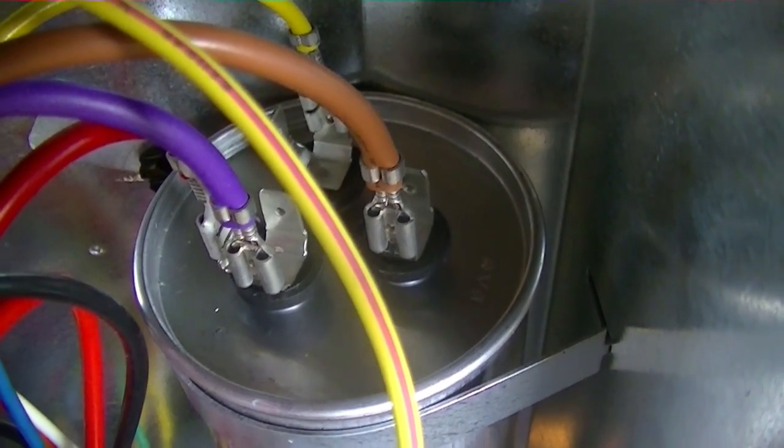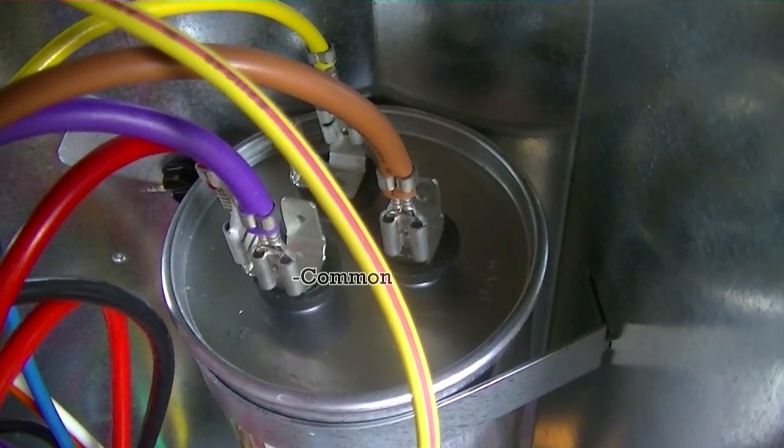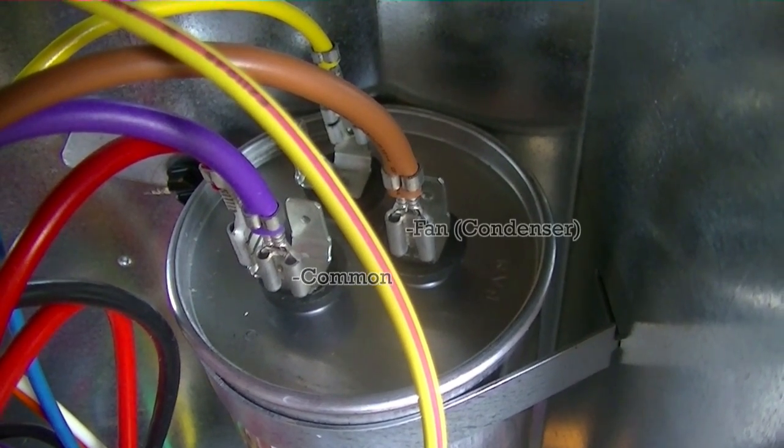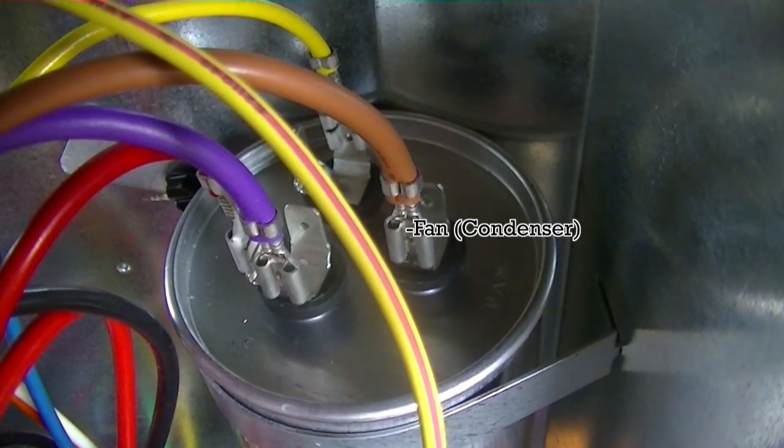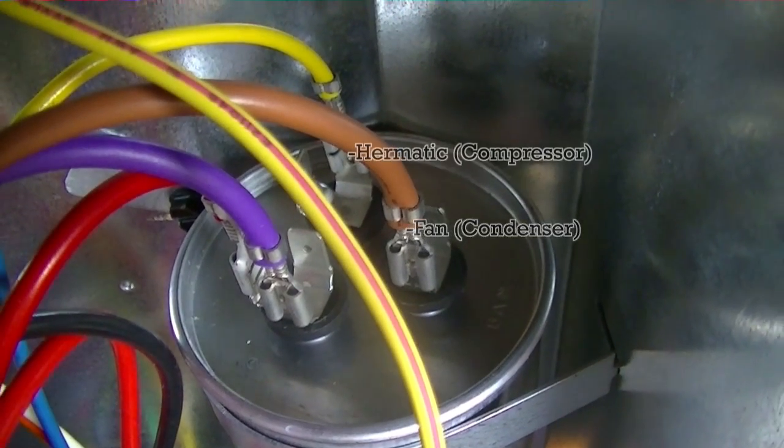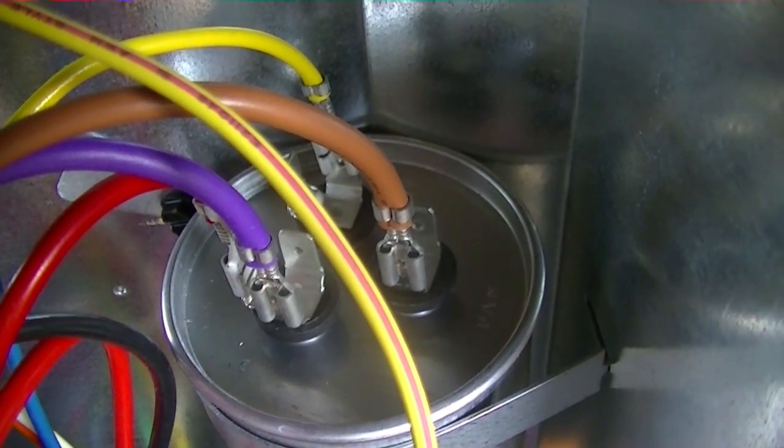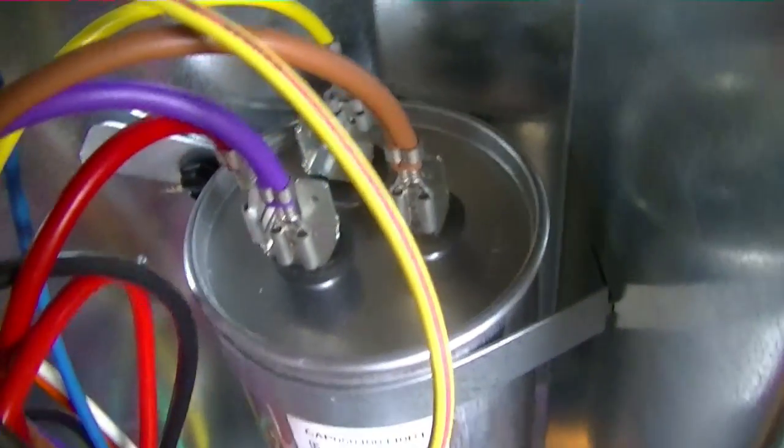Here we have our capacitor. We have the purple and red going to our common terminal. We have our brown going to our fan terminal, and our yellow going to our hermetic terminal. Hermetic is hermetic compressor, it just refers to the fact that it's hermetically sealed.